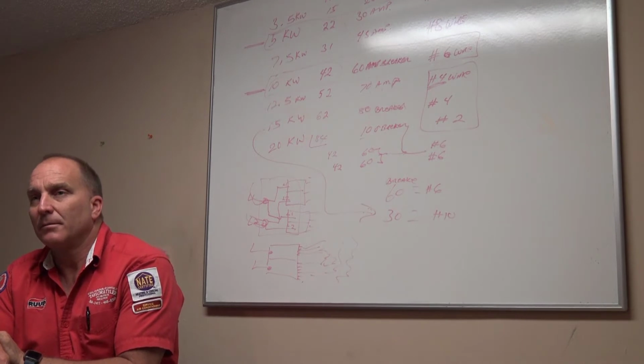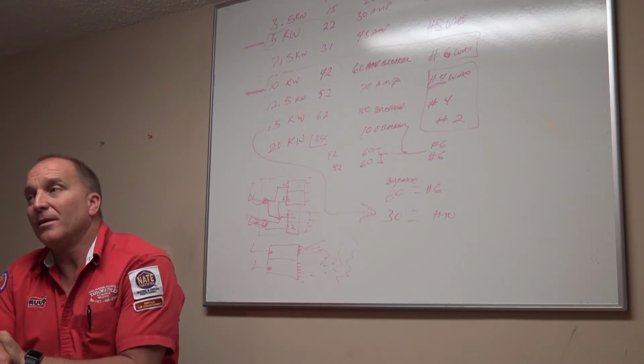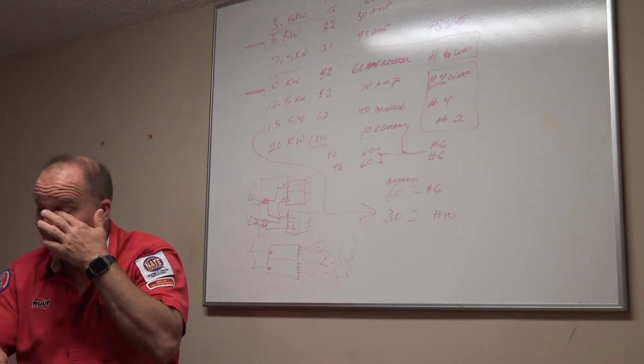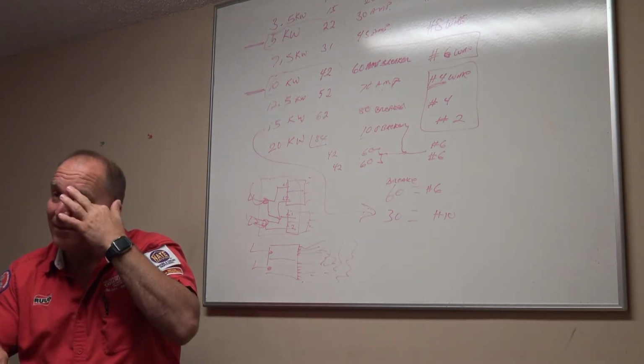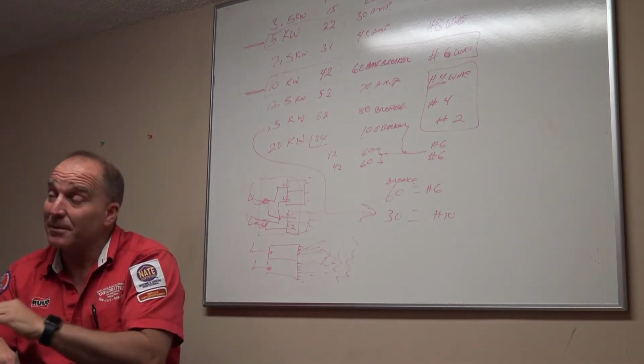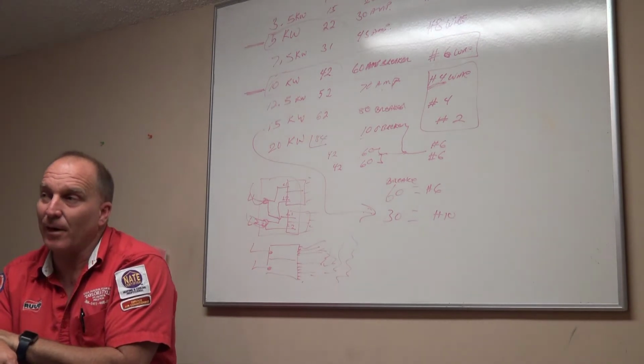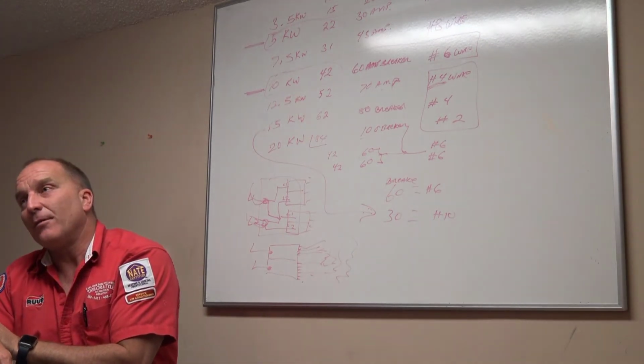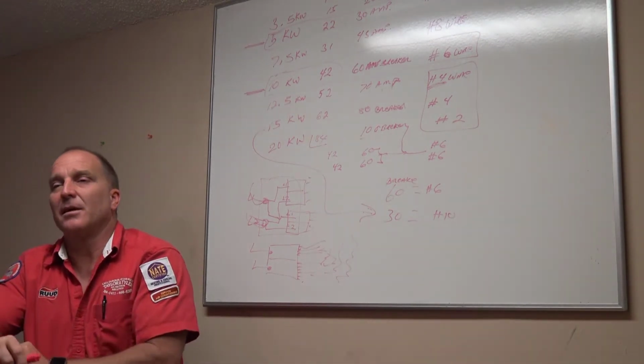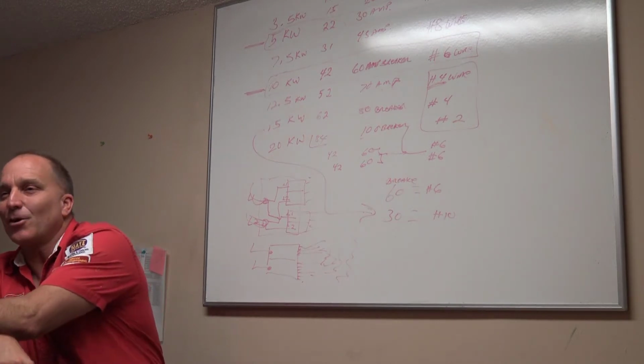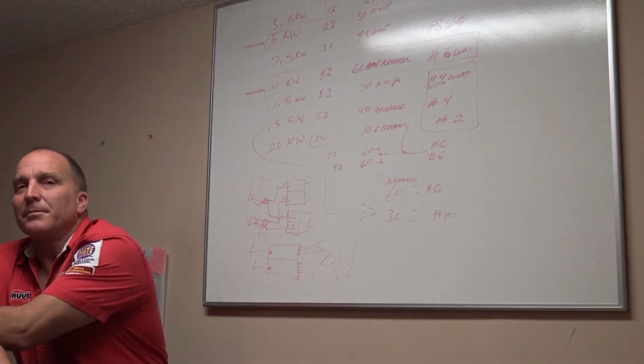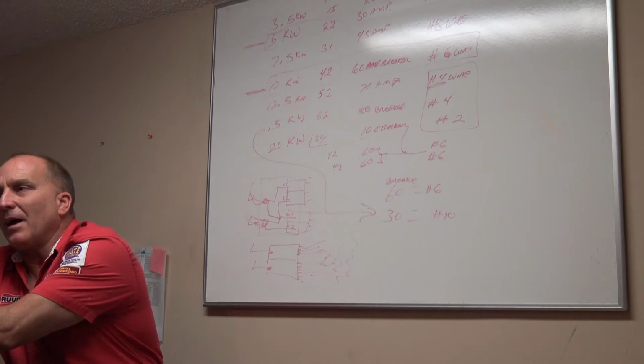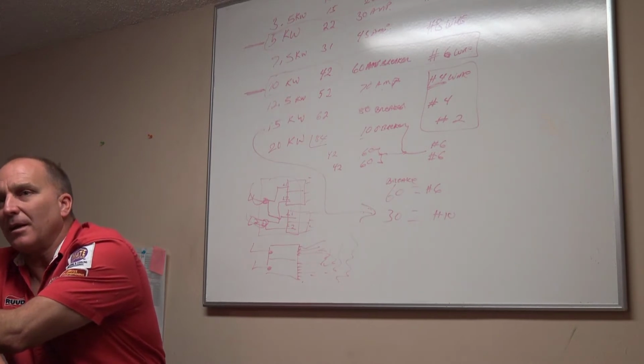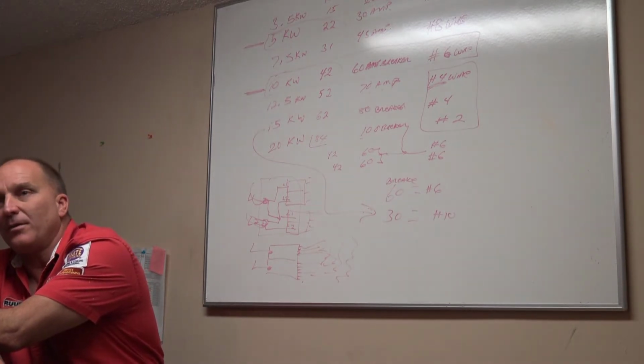conditions. Do we have cold weather conditions here? No. We have a couple weeks out of the year sometimes, right, that we need a heater, right? So, if you live in Chicago, where my son's living at now, he says it's starting to get cold out there already, I bet you can't have a 3-ton system with 10 kW heat out there. I bet it's 15 kW.